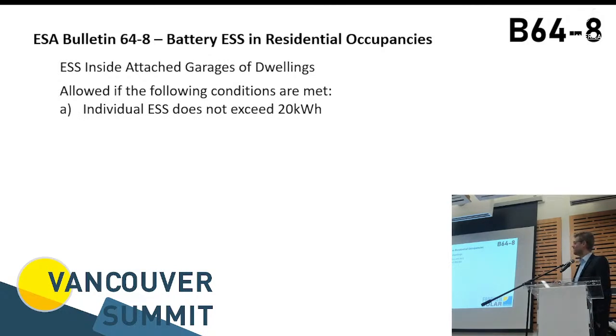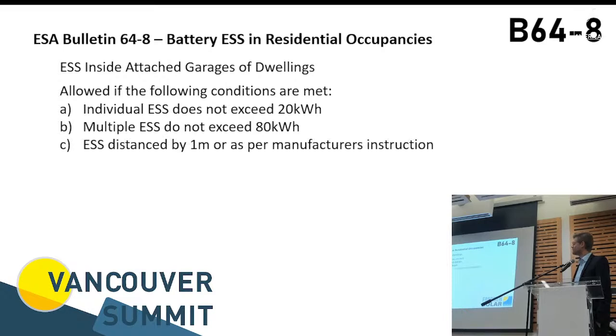Same thing applies. You have 20 kilowatt hours in one system. You cannot exceed 80 kilowatt hours now, because you're under the attached portion of it. Same distance requirements of 1 meter or what the manufacturer says. And that is my recommendation in general. If the customer has a garage available, that is probably the best spot to put it, because that's the highest likelihood to convince your inspector that you met all these requirements, and you don't have to go into designing the room to be fire rated and have the smoke alarm and fire alarm interlinked and all these little hoops to jump through. That's just the best way forward.